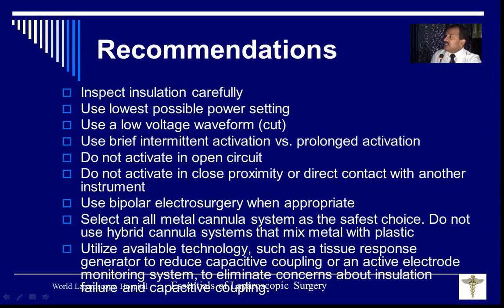Use brief intermittent versus prolonged activation. Never press your paddle in one go for more than 3 seconds. You can give 2, 3, 4 times, but intermittent. Do not activate in open circuit. Hook, look and then cook. Never activate your paddle if the tip of the instrument is not touching the tissue. Do not activate in close proximity or direct contact with another instrument, to prevent direct coupling.